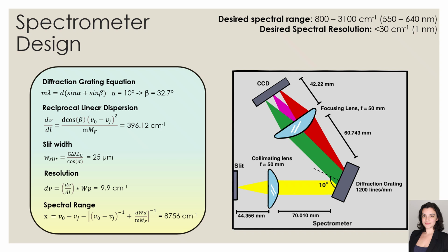The final component on the illumination optic side is a 75mm focal length condenser lens that will focus an 18mm beam onto the slit. This results in an F number of 4.16. In the spectrometer design, I carefully matched this F number through my choices of lens diameters and focal lengths to increase the light throughput of the system.